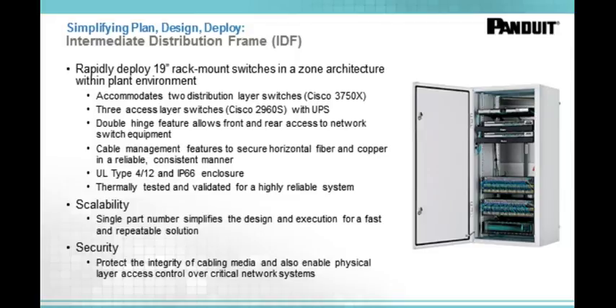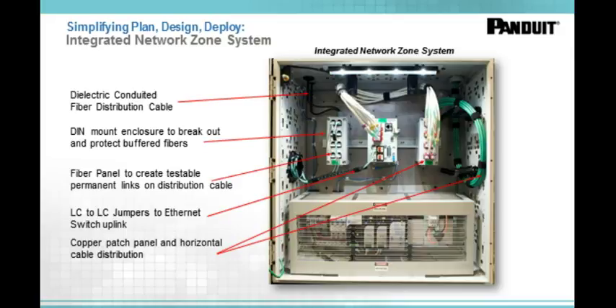You may need a consolidation point for 19-inch rack equipment where you can put a stack switch into the enclosure, yet have it industrially hardened—NEMA, UL Type 4/12, IP66 enclosure with cooling options, air conditioning, and so on. This can be rapidly deployed as a building block, all pre-configured with the physical infrastructure, so you just install your switching, allowing a much more rapid, scalable, and secure deployment since it's a locked enclosure.